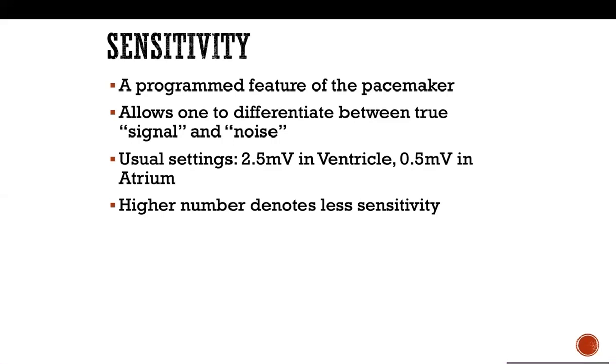So first, you need to check exactly what the device is sensing. And second, you need to set the sensitivity at least at 50% of the R wave. So you'll be able to see the majority of the R waves, so you don't miss beats.